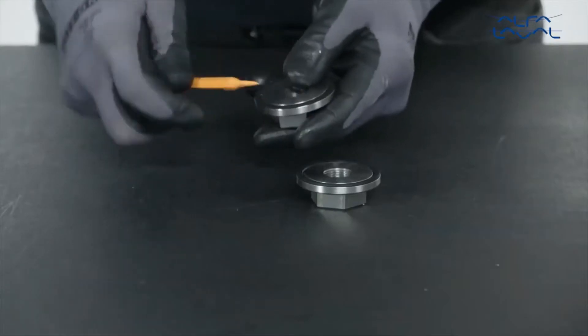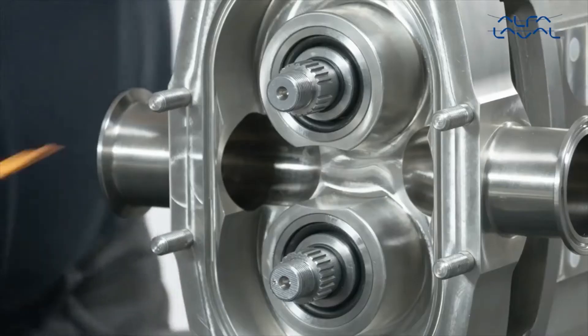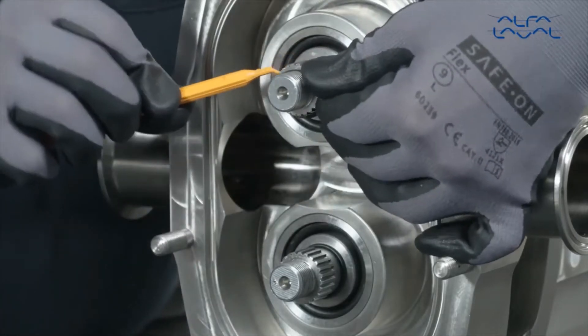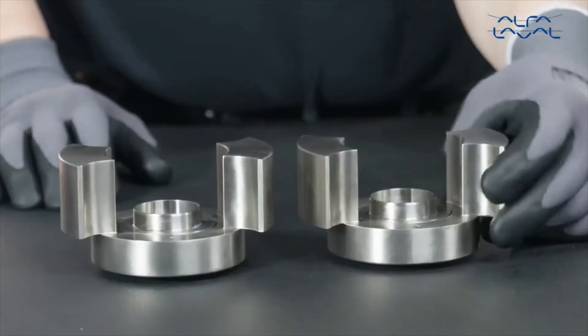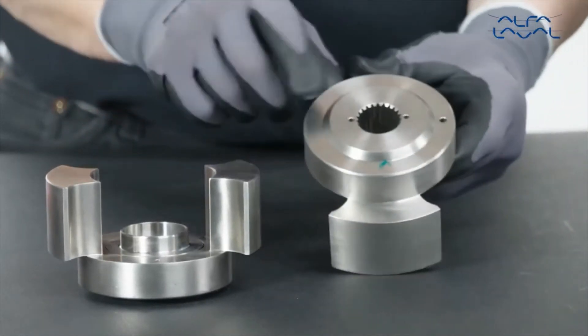Remove the rotor nut O-rings. Then, remove the rotor shaft O-rings. Remove the sleeve from the rotor using a small screwdriver, if required.